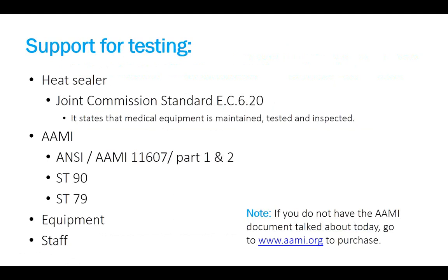Well, many people use Joint Commission. In Joint Commission, there's a standard, EC 6.20, that states all medical equipment is maintained, tested, and inspected. For any of you who have a heat sealer in your department, your biomed department, an older term I'm just used to using, has probably placed an equipment sticker on it, and that's in the inventory of your hospital. That means it's tracked and monitored. Most people just do electrical testing on it, but there's a way you should be making sure you get a good seal, and you document it.